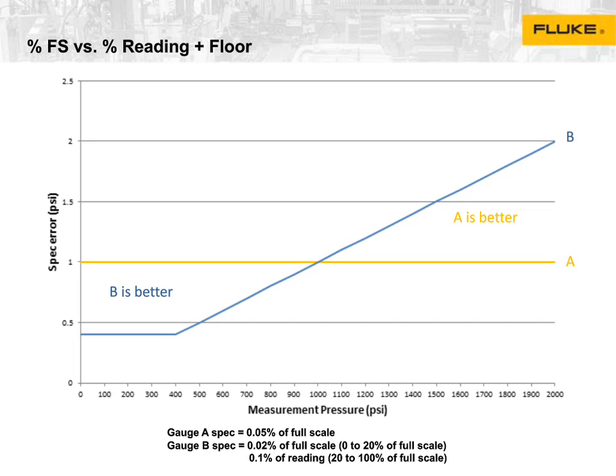And so that sort of discussion around that specification is something that we see a lot, and people will say, well, this one's percent full scale and this one's percent reading. How do I know which one is better? And so the thing you need to know is that the closer you are to the higher end of the range, the better the full scale gauge is going to perform, and the closer you are to 0, the better the percent reading gauge will perform.